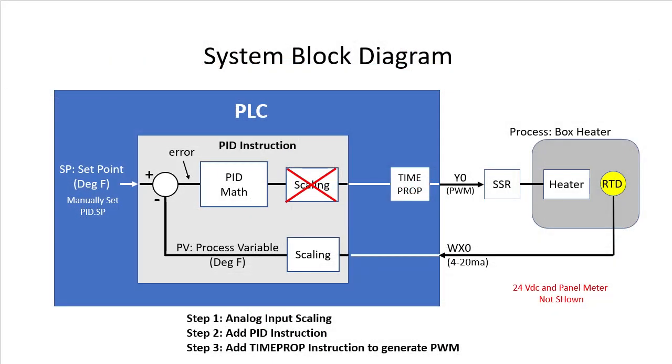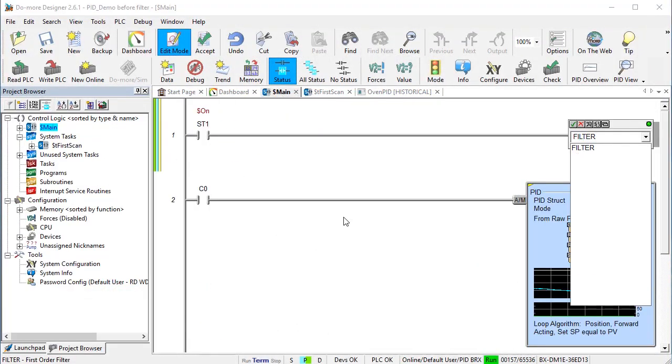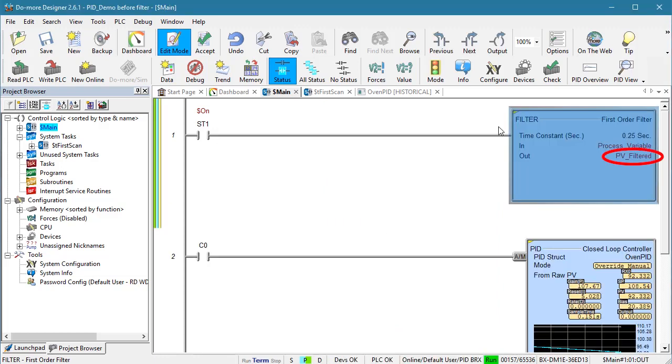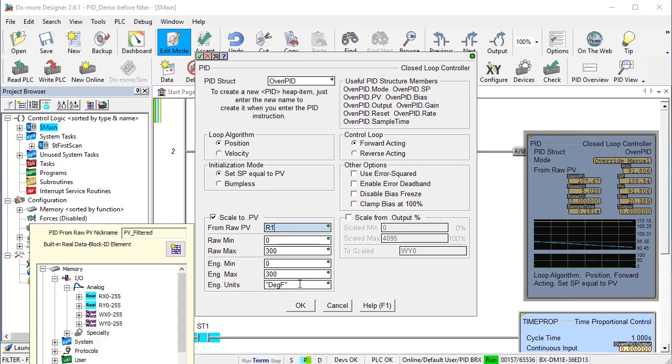To fix the noisy signal, we'll just add a filter to get rid of the noise before we do our PID calculations. Let's add the filter instruction right before the PID instruction. Our RTD sensor has a 1 second response time so we can filter anything that changes faster than that — I experimented and found that a quarter second filter time was more than enough. We want to filter our noisy process variable in WX0 and put the result in R1, which I already named Process Variable Filtered. We also need to go into the PID instruction and tell it to use the new Filtered Process Variable.